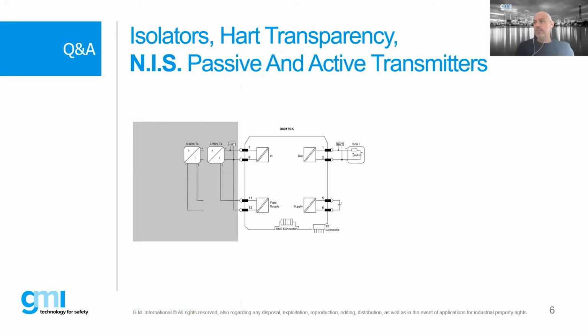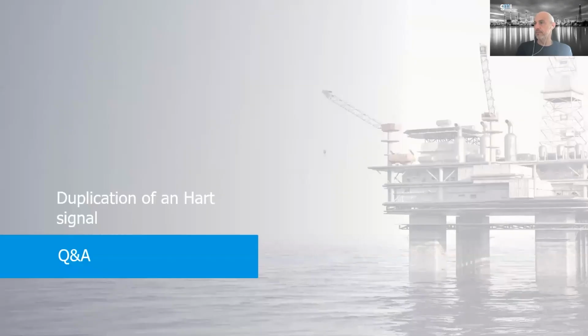There are other units that also power the transmitters, so not only get the active signal, but are also able to power the transmitters, powering and receiving the signal. This is a unit used for non-ATEX applications, so it's only for safe area application, because the power in this case is higher than the allowed for hazardous area.